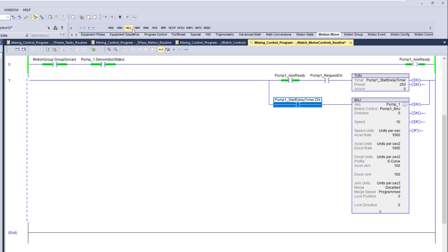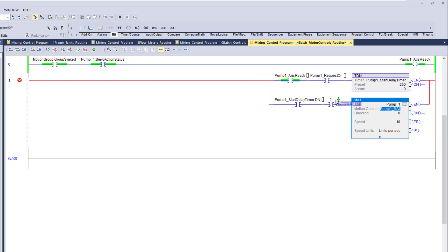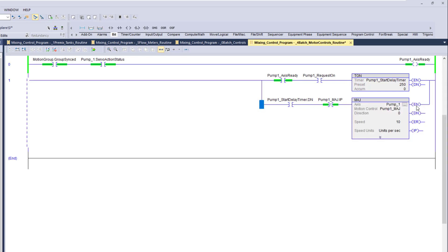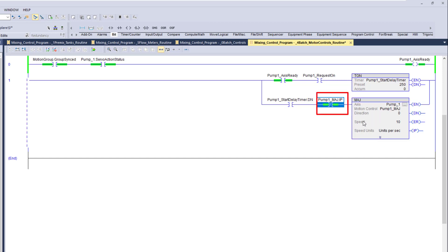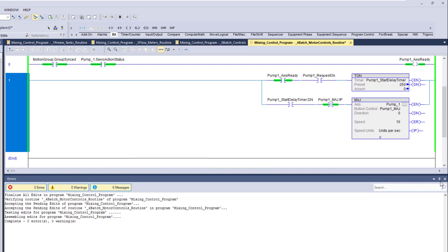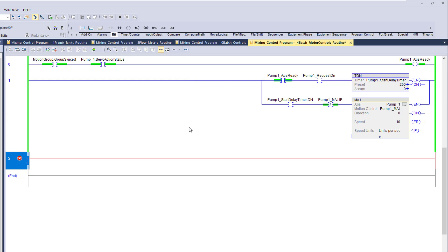We still need to add another feature. We'll grab a bit and say that the pump MAJ is not in progress (IP). There are several bits on motion commands: enable, done, error, and IP — in progress. We don't want to keep commanding this if it's already in progress.